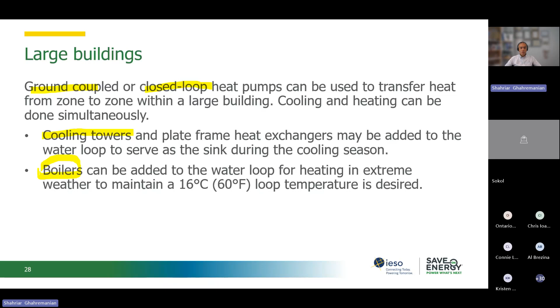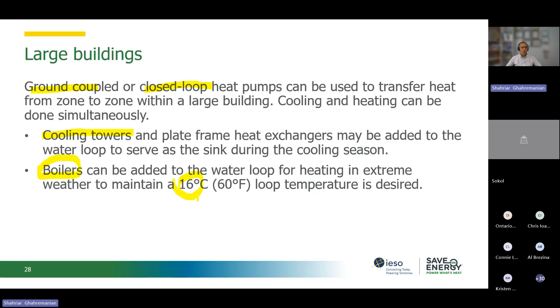We can add cooling towers to these ground coupled or closed loop heat pumps to increase the efficiency and also provide more support or supplement to the amount of heating or cooling that we need, if we require it in extreme conditions. In extreme cold temperature, because we need to maintain the water temperature in the loop at 16 degrees Celsius, sometimes we need to add a boiler for supplement and make the heat pump a hybrid system. So then it can switch to use the boilers. But this is again for times when the outdoor temperature is, let's say, minus 25, minus 30 degrees Celsius. This is for those times that we can run our boilers for heat.